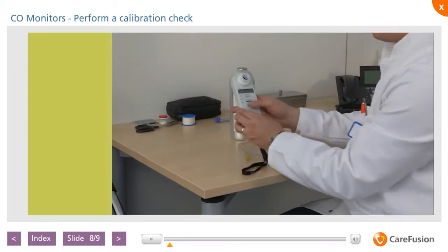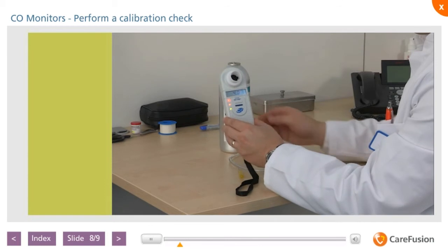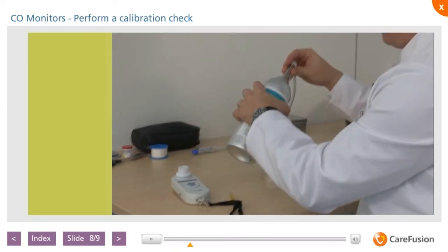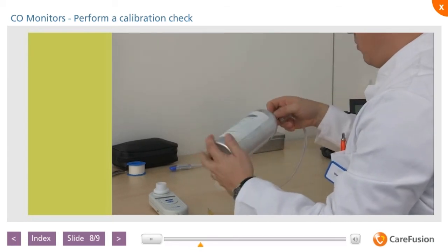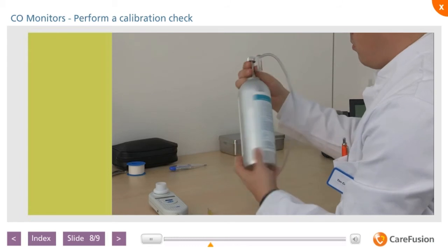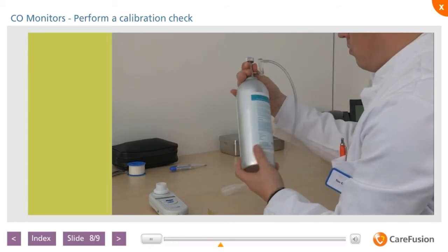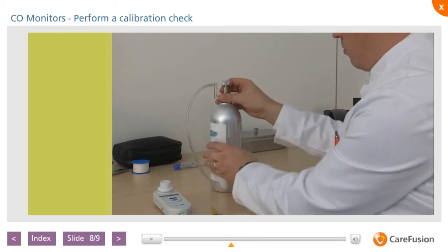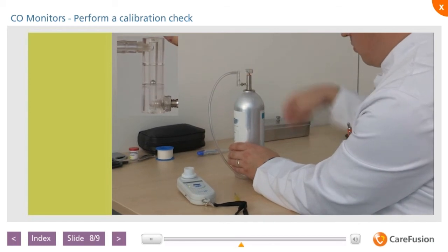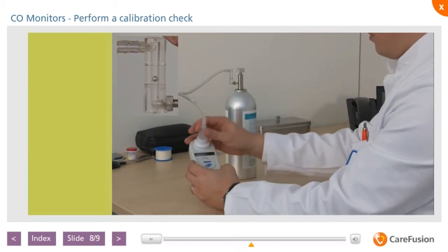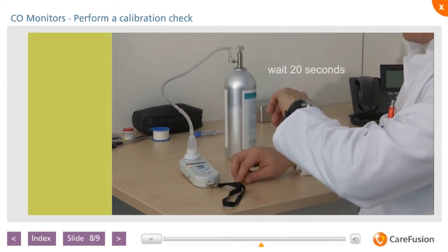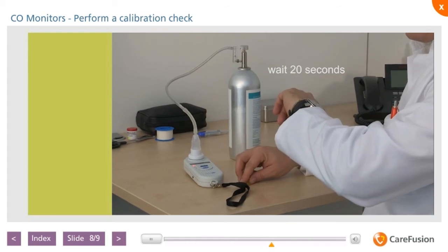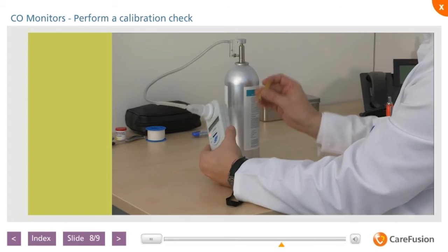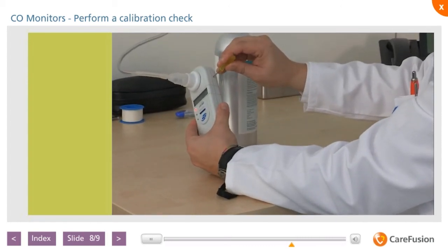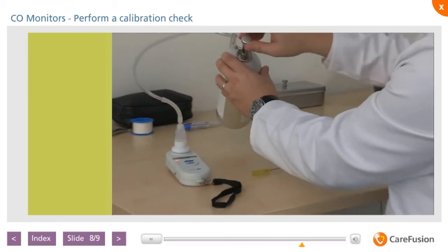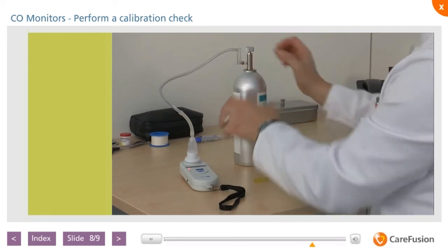To perform a calibration check, push the slide switch to the CO ppm position and wait for the unit to display 0. Connect the gas cylinder to the regulator valve. It's recommended that only CareFusion calibration gas supplied in 20 parts per million is used. Turn the regulator control valve to the point where the ball of the flow monitor floats in the middle of the Perspex guide. Connect the plastic tubing to the calibration adapter supplied. Allow the gas to flow for 20 seconds. Insert the calibration tool into the side of the CO monitor. Turn the gas regulator off and remove the calibration connector. The unit should now display 20 ppm and calibration is complete.